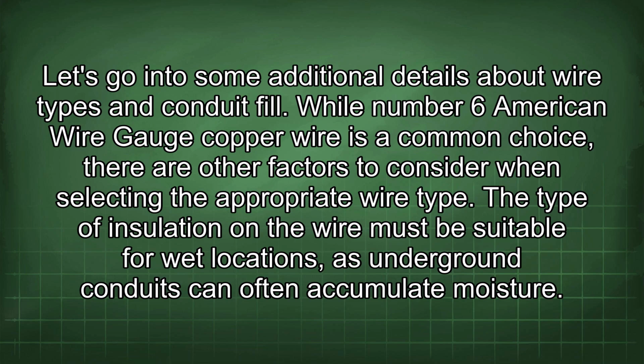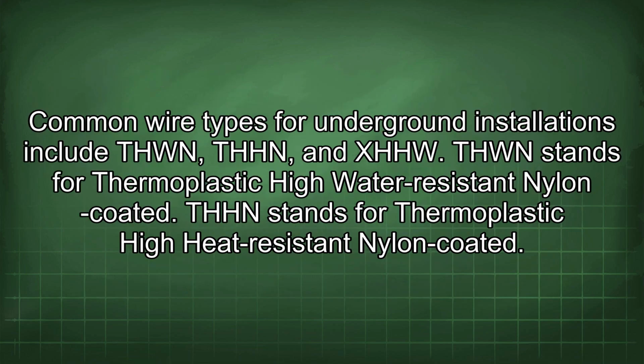Let's go into some additional details about wire types and conduit fill. While number 6 American wire gauge copper wire is a common choice, there are other factors to consider when selecting the appropriate wire type. The type of insulation on the wire must be suitable for wet locations, as underground conduits can often accumulate moisture. Common wire types for underground installations include THWN, THHN, and XHHW.